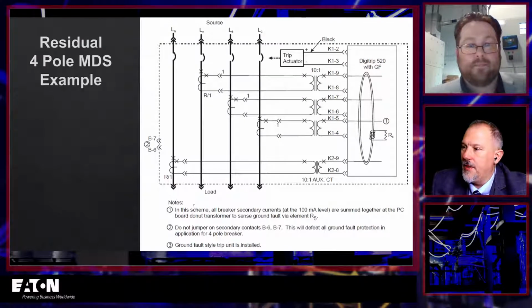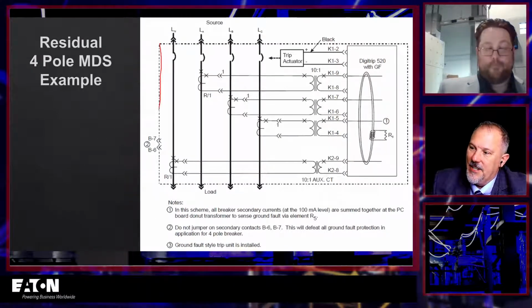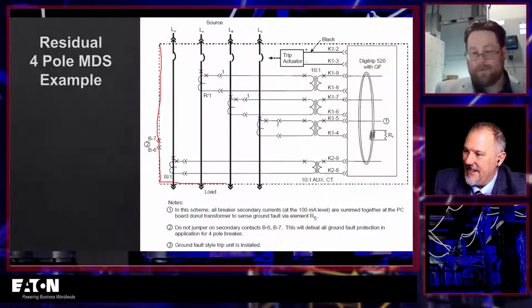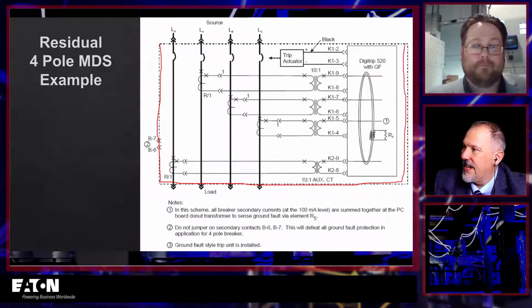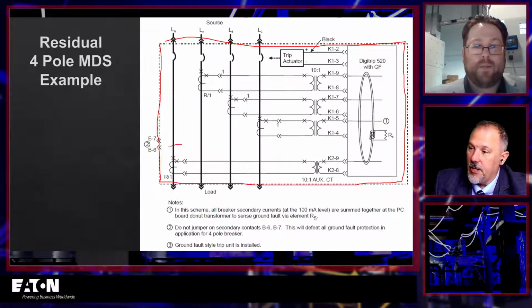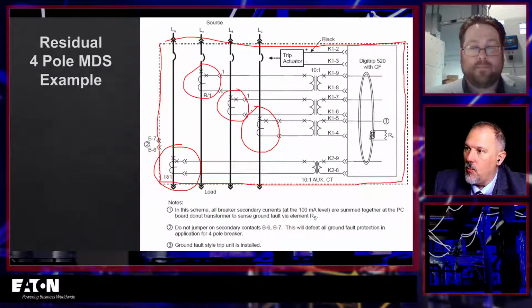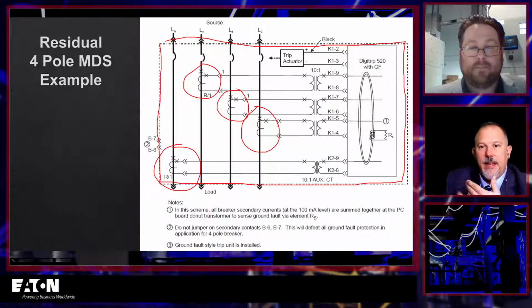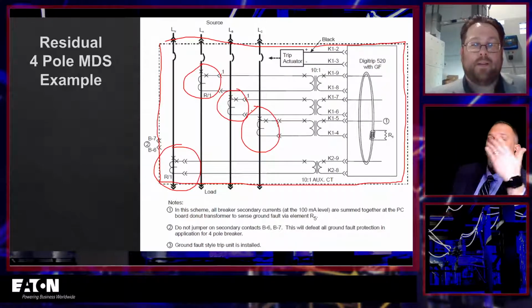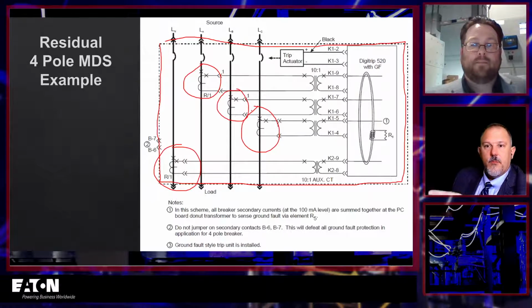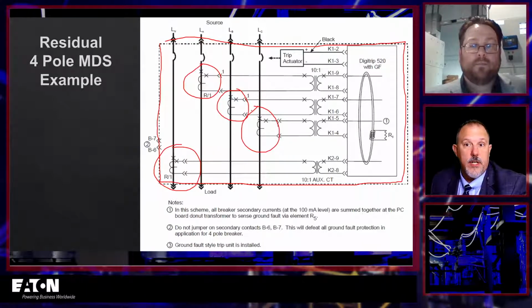Now, how would you, and now this is the breaker, right? So here's your breaker. This is exactly what we were just talking about. There's your circuit breaker, and now you have a 4-pole circuit breaker, and this CT, and this CT, and this CT are all in one. And this is where I would hear arguments that, look, testing this circuit breaker, it was tested, and let's say it's a molded case circuit breaker, because remember we're talking 1,000 amps and above. I can have a 1,000-amp molded case circuit breaker.